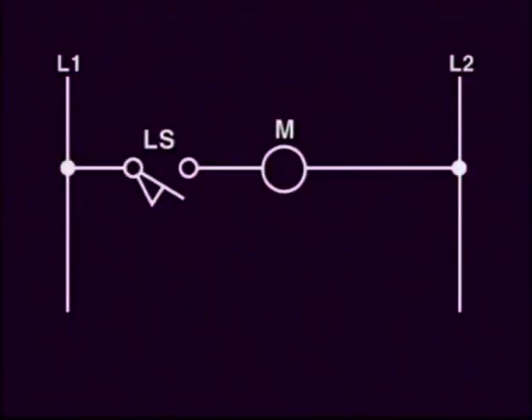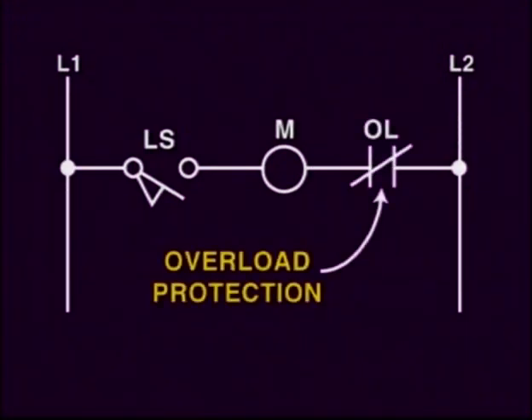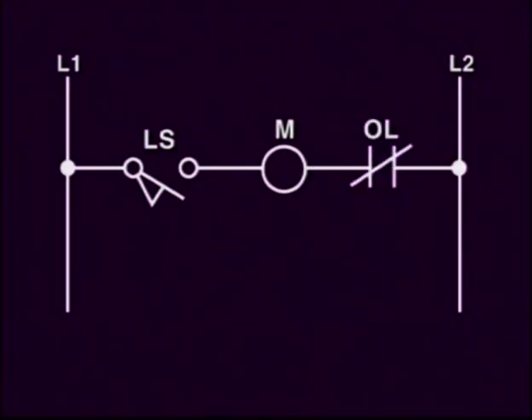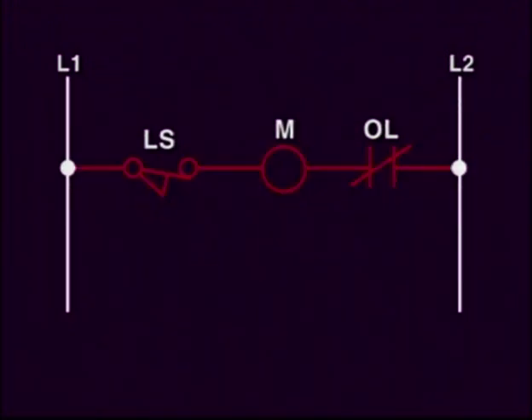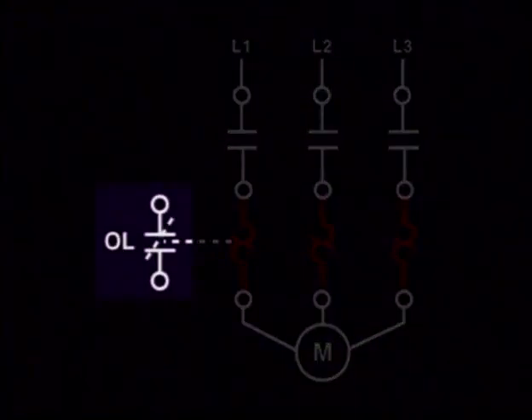The overload protection is shown in the ladder diagram representation like this, where the normally closed overload contacts are right after the starter coil. These contacts will open if the overload relay detects that there is an overload situation which is causing the motor to pull more current. This can happen if the motor is experiencing a locked rotor situation, in which case the motor must be disconnected from the circuit, otherwise it could burn out.